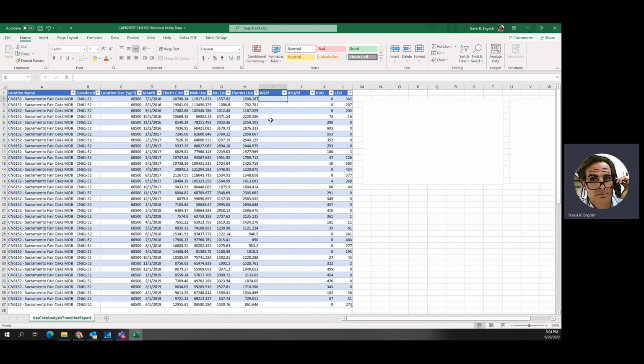We'll do this based on 300 hours per month, since this is a medical office building, and we can talk about that later. So for watts per square foot, I take my monthly kWh, multiply times 1,000, divide by the square footage, and divide by 300 hours a month. This gives me a watts per square foot number.